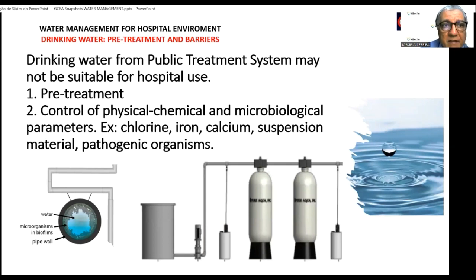The first defense of your hospital water system is the pre-treatment. The system must block or control unwanted physical, chemical, and microbiological elements present in drinking water. Examples of these elements are chlorine, which must be controlled, iron, calcium, suspended materials, and pathogenic organisms. All this must be eliminated.